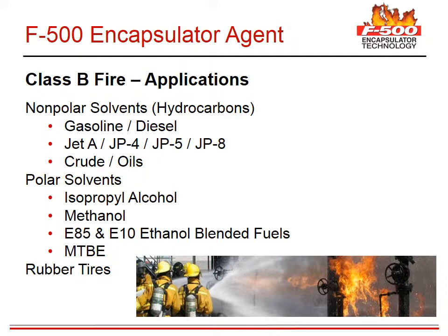Later you will see a video where F500 extinguishes a high-temperature Class D magnesium fire. This capability is due to F500's remarkable ability to cool. F500 has also been tested by Con Edison and FDNY for use on Class C electrical fires in a standoff leakage test. F500 at 3% with water can safely be used on an electrically charged transformer fire at 345,000 volts with a 40-degree disperse spray pattern.